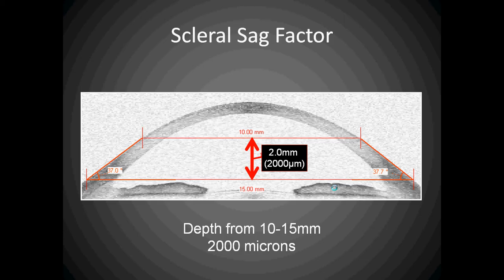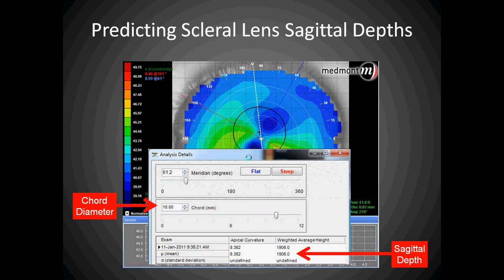If our corneal topographer can measure the sagittal depth from a 10mm chord to the peak of the eye, then we have a very powerful tool for predicting the initial scleral lens required. Because we know that the average sagittal depth of the eye from a 10 to 15mm chord is approximately 2,000 microns, and the Medmont will be capable of measuring that sagittal depth.